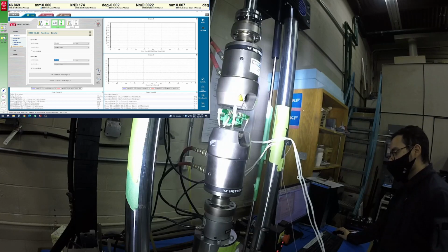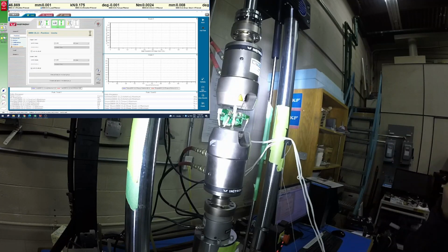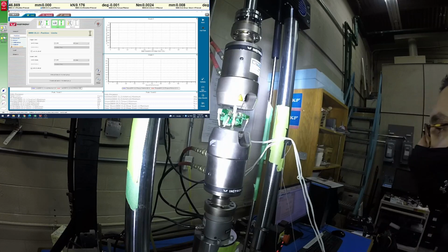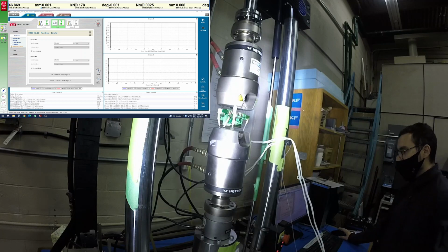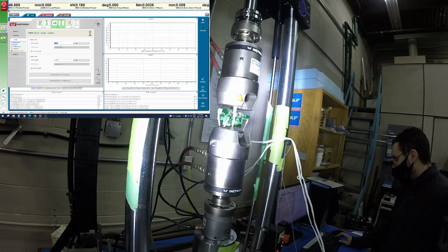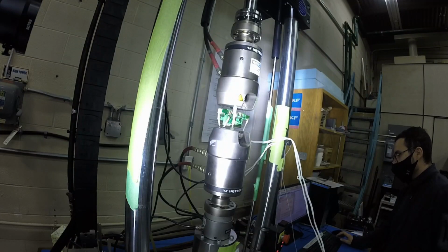And to enable the limit, you're just going to select this checkbox here. And you'll see when that happens, as you select and deselect, you actually enable each of these lights to occur here. So you can have up to four limits in the upper and lower threshold region for the axial and the rotational directions. So we have a limit set up for position. We have one set up for load here. Let's say we're going to go maybe to 1.5 kilonewtons, negative 1.5, enter.